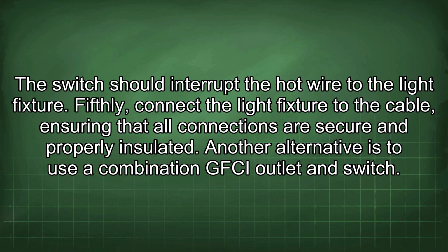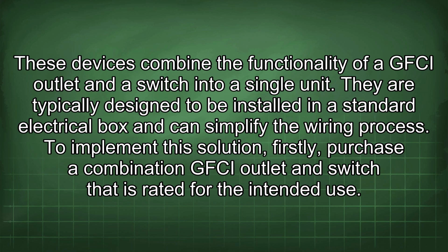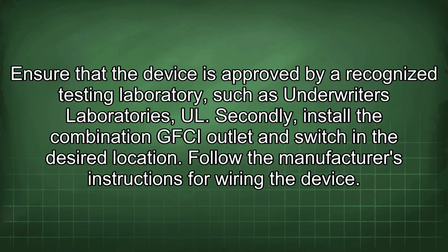Another alternative is to use a combination GFCI outlet and switch. These devices combine the functionality of a GFCI outlet and a switch into a single unit. They are typically designed to be installed in a standard electrical box and can simplify the wiring process. To implement this solution, firstly, purchase a combination GFCI outlet and switch that is rated for the intended use. Ensure that the device is approved by a recognized testing laboratory, such as Underwriters Laboratories, UL.